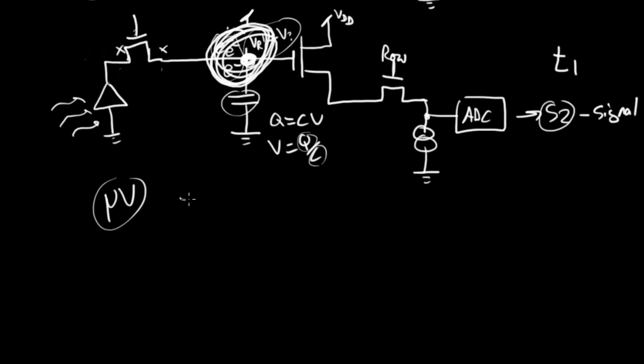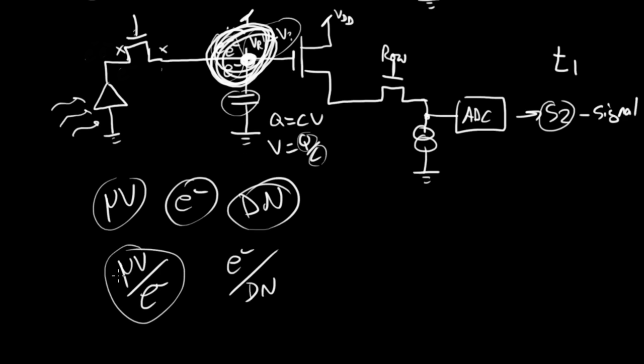And there will be some conversion gain for the system in terms of microvolts per electron or electrons per digital number. And this in particular, microvolts per electron, is just mostly determined by this integration capacitor there. The electrons per DN is determined by a lot more.